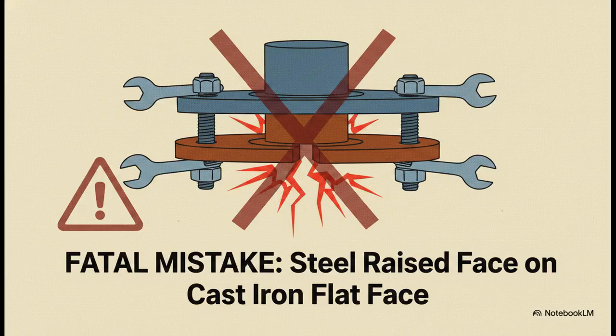Now, pay attention here because this is absolutely crucial. This is the golden rule of piping. Never, under any circumstances, bolt a raised face flange to a flat face flange. If you try to mate a steel raised face to a cast iron flat face, that raised section acts just like a fulcrum. When you crank down on those bolts, the concentrated load will literally snap the brittle cast iron housing right in half. And trust me, nobody wants to be the one holding the wrench when that happens.